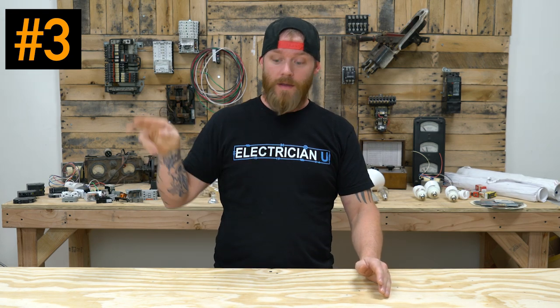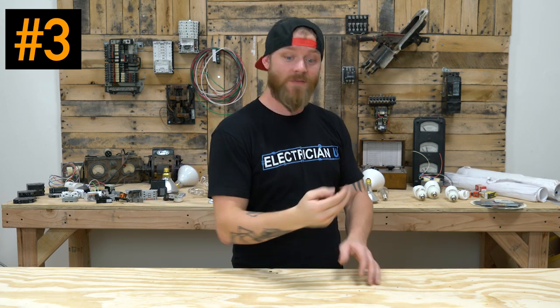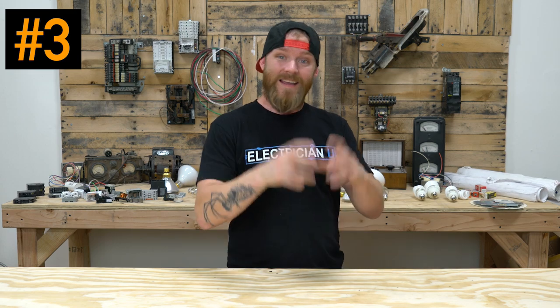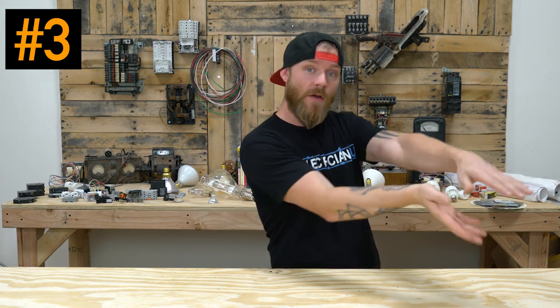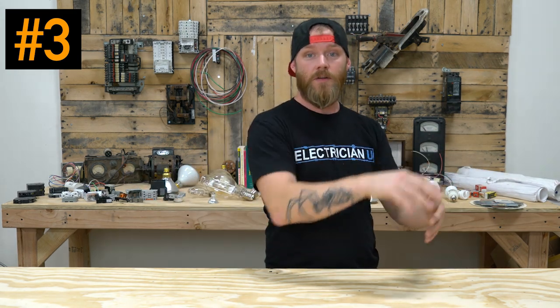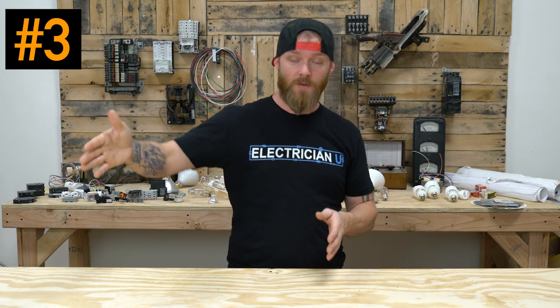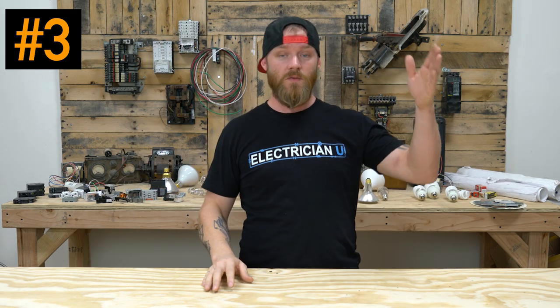So feeders can come from a service panel, you know, a breaker, leave, go up into another disconnect, leave that disconnect, and can go into a transformer. It's all still feeders at this point. It can leave a transformer and then go to another panel. All of that is feeders, from that first overcurrent device at the service to the last overcurrent device at the last panel. Everything in between that is feeders.